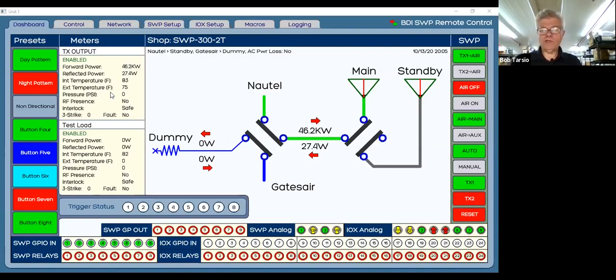This is a 2-switch controller, so we have 2 switches here. You get a view of the positions of the switches and their status, and you notice the power measurement is right where it's supposed to be, which is where the directional coupler is in the line between the two switches. Then you have another meter here showing no power, because apparently the GatesAir transmitter is turned off, but the Nautel is running 46.1 kilowatts into the main antenna.